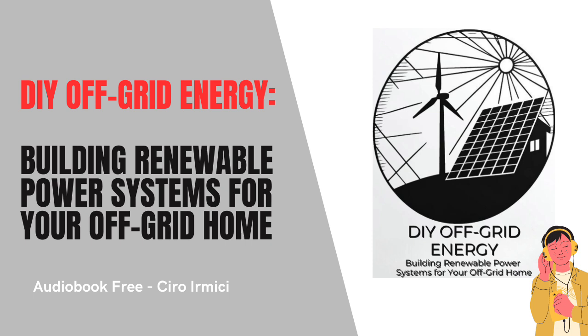Battery maintenance is also crucial. Regularly checking the charge levels and ensuring that batteries are operating within safe voltage ranges will help extend their lifespan. For lead-acid batteries, periodic equalization charges may be needed to prevent stratification and sulfation, common issues that reduce battery performance. Lithium-ion batteries, while more maintenance-free, still benefit from occasional performance checks to ensure they are charging and discharging correctly.